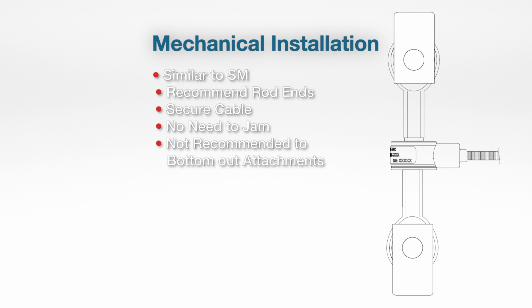As you mentioned, pay attention to the cable. These have pretty good strain relief on them from the factory, but that cable can still often influence your measurement if you're not paying attention to how it's secured, especially in dynamic tests where you may have some inertial influences on the measurement you're taking.